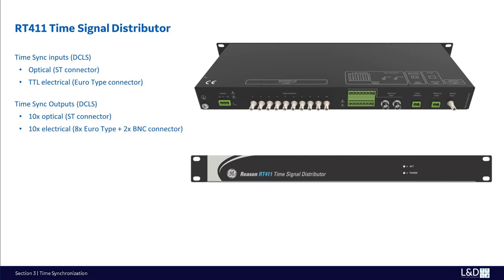Typically, the RT411 is installed as a port multiplier, acting as a slave to time signals received from a GPS clock. There are 2 types of DC level shift time sync inputs: optical with ST connector or TTL electrical with Euro type connector, which can be selected by a jumper. For the 20 DCLS time sync outputs, there are 10 optical ST connectors, 8 Euro type electrical, and 2 BNC connectors.